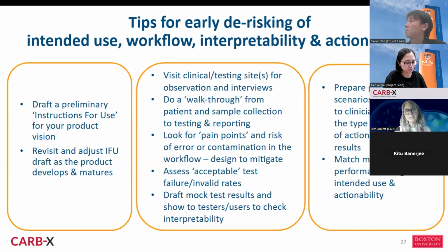This middle column is, go on a visit if you can. Go to the places where you want your test to be used. See what the environment is like. See what the conditions are like. A lot of times we have assumptions about who will use the test, what their day looks like, how they're going to implement it, and we don't always get it right. So whenever you can, go and see it in person. Look for the pain points that you might be able to design mitigations for. Understand what happens if you have a failed test. What impact does that have on the workflow and the people running the test, or the impact on the patient for those delayed results?